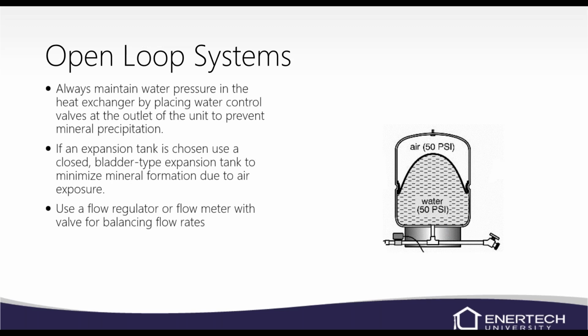If you're going to use an expansion tank on an open loop, use a closed bladder type expansion tank to minimize mineral formation due to air exposure. If you've got a flow restrictor or a flow regulator in the system and it's bigger than what you really need, you can always use a valve, like a ball valve, to kind of balance the flow rate a little bit if you need to.